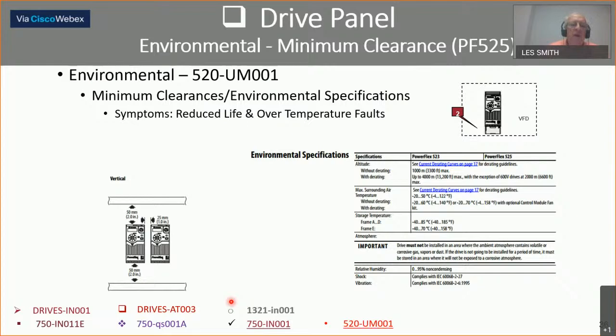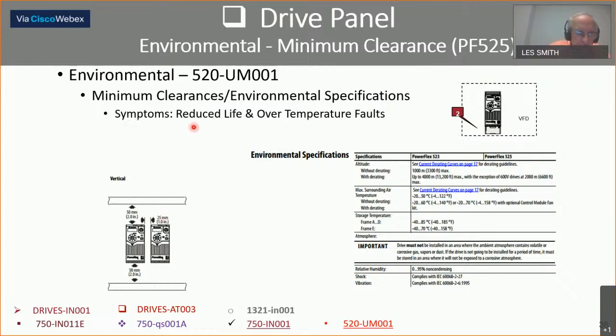For the 520 drives, note the spacing: two inches here and two inches on the other side. Just because a duct has holes in it and wire doesn't necessarily mean that air will flow through. Put a standoff on these drives and mount them above the ductwork so you get good airflow — you will extend the life of the drives. If you have too much heat in the enclosure, it will dry out the capacitors in the drive and they will fail prematurely.